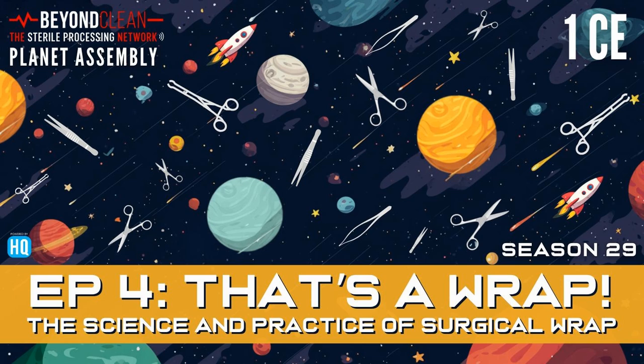Awesome question. Surgical wrap, some people just look at it as a cover, like, okay, it's just covering the instruments, but it's more than that. It's a tool for infection prevention. I know a lot of people refer to it as surgical wrap, but it's also referred to as sterilization wrap. And that's the type of material used to enclose medical instruments or devices before sterilization. Its main job is to act as a sterile barrier system, allowing sterilizing agents such as steam, vaporized hydrogen peroxide to penetrate while preventing contamination afterwards, right? So after sterilization, it should be able to maintain its sterility until the point of use, allowing the OR to use it, right? Per its validated MPI time point as stated in the IFU for that specific sterile barrier system.